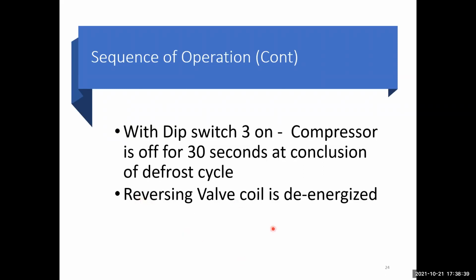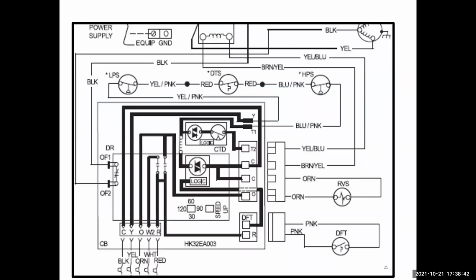Reversing valve is de-energized and the compressor will start back up. This is another wire diagram. It's going to be the same situation as far as going through the wire diagram. What I really wanted to let you know about is here's the T2 that we didn't have on our last wire diagram. And this is what's going to go ahead and control the compressor time delay. And this is also going to lock out for the 30 seconds at the activation and termination of the compressor.